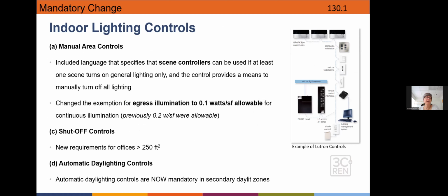For the indoor lighting controls, again, on the surface we know we're going to have indoor lighting controls, and it appears that too much hasn't changed other than maybe the threshold triggering those controls a little bit sooner than they would have under the previous code cycle. So now there's shut off controls for offices greater than 250 square feet. That was part of it before, but now there's some new requirements that go along with it. And there's some automatic daylighting controls that are now mandatory in the secondary daylight zone.